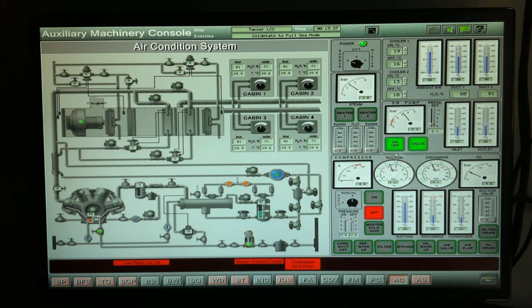Open the valve, start the pump. And then the aircon compressor, master solenoid open, condenser shut off, filter open. Then start your compressor, crack open around 10%, then set it to automatic running. And then wait for the oil drain to open. Once the solenoid to the oil drain already opens, you could gradually open your suction valve to 100%. Then leave it automatically running.